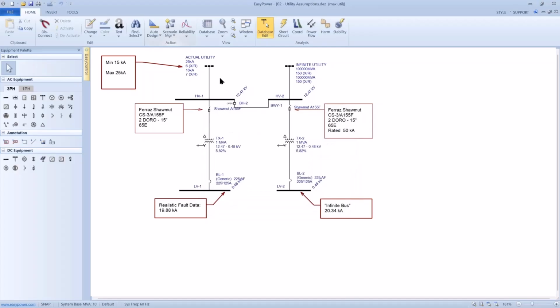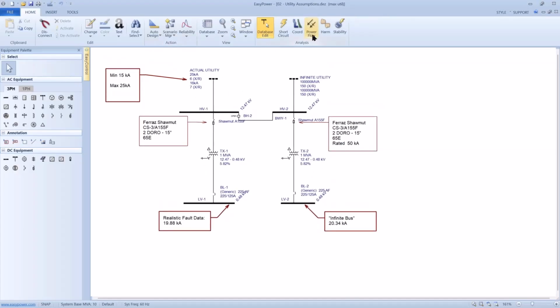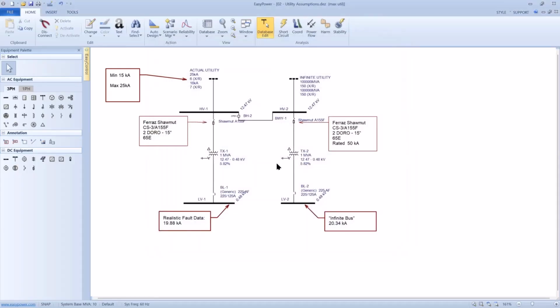And so if I look at these, look at my max, I don't change anything but the value for the utility. So under the base case, I had 20,000 amps, and I based that on the value of this installed fuse. If we look at how the fuse is rated, it's rated for 50,000 amps. So a conservative value might be, for grins, half of that number. So that's where I got the 25,000. Now there may be more accurate ways to estimate it, but that's just where I started. And then I saved in a max utility scenario a 25,000 amp source, and I saved in the minimum scenario a 15,000 amp source.